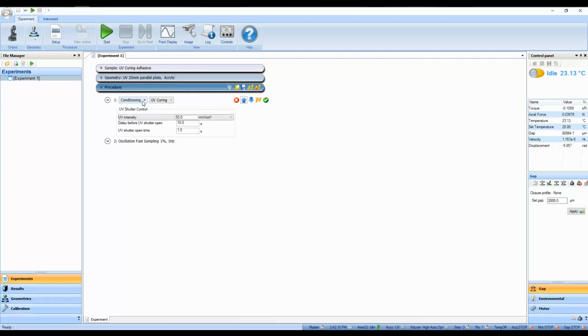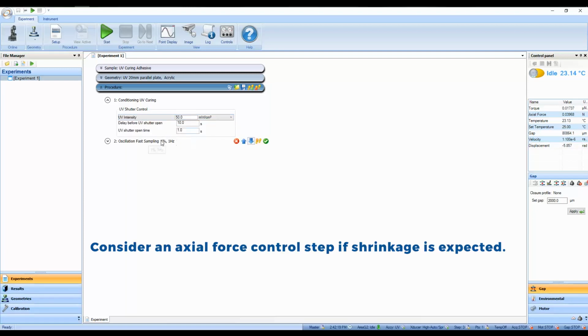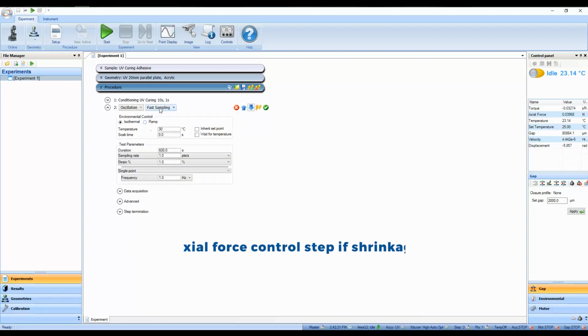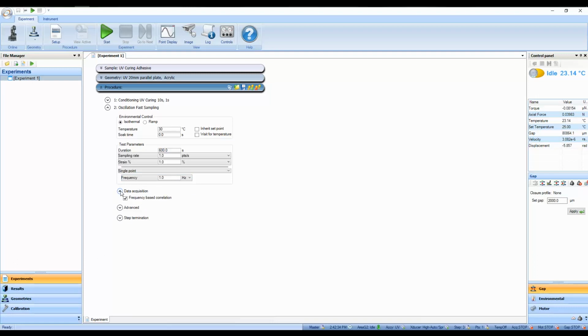To set up a test, select Conditioning UV Curing step and set power, the delay time, and duration for the UV exposure. Follow the conditioning step with the oscillation time or oscillation fast sampling. Select the temperature if using a Peltier system, the duration, sampling rate, strain amplitude, and frequency. Finally, select the sampling cycles option.